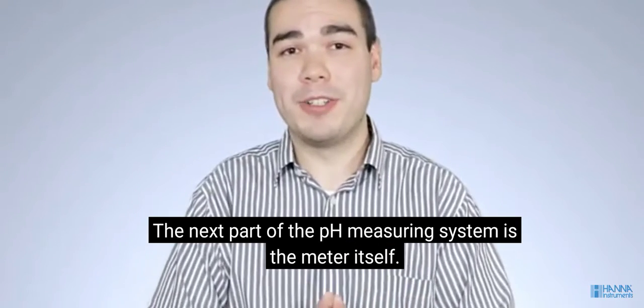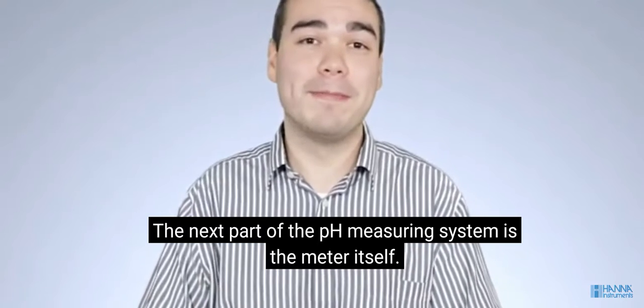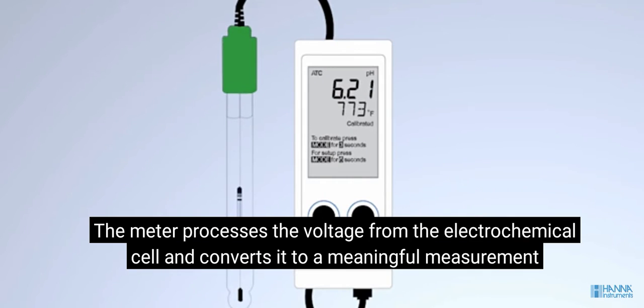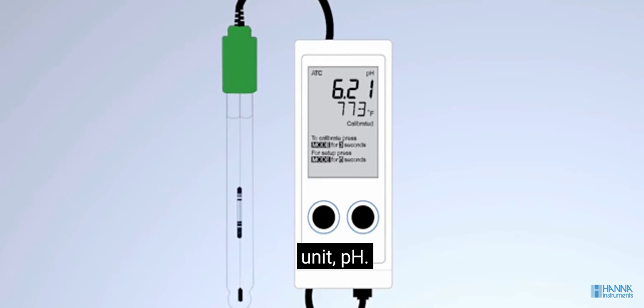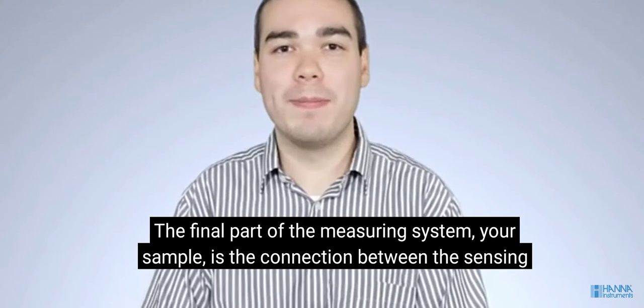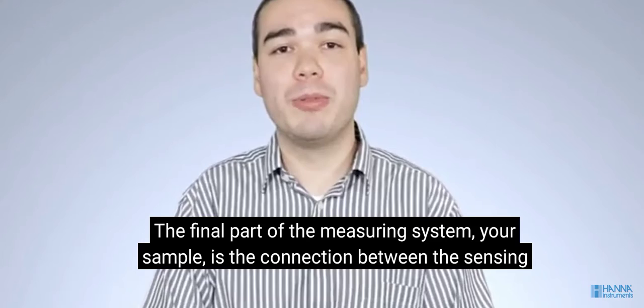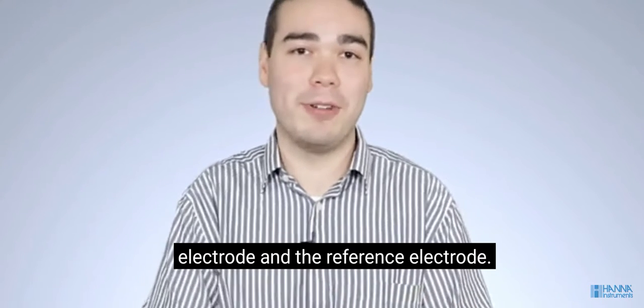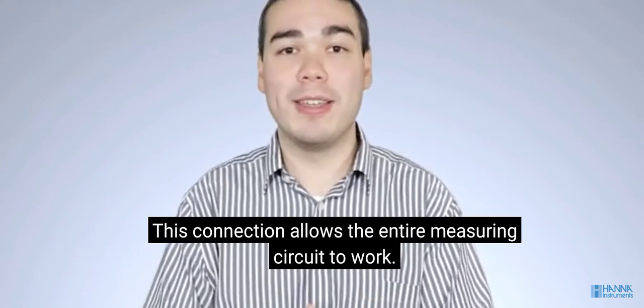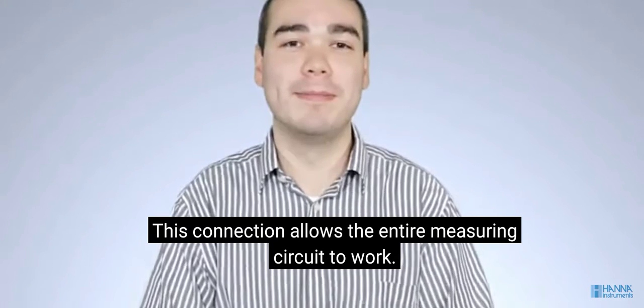The next part of the pH measuring system is the meter itself. The meter processes the voltage from the electrochemical cell and converts it to a meaningful measurement unit, pH. The final part of the measuring system, your sample, is the connection between the sensing electrode and the reference electrode. This connection allows the entire measuring circuit to work.